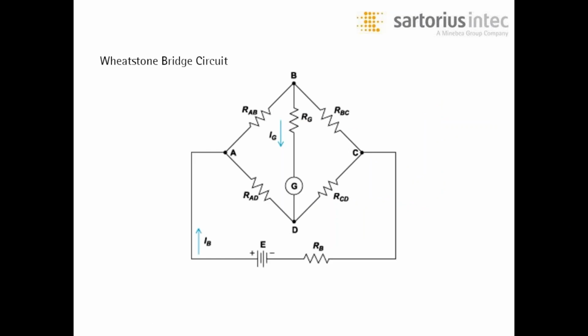As you can see, when they're configured in a Wheatstone bridge with 4 separate resistors connected as shown in a network, an excitation voltage, usually 10 to 12 volts, is applied to one set of corners, and the voltage difference is measured between the other 2 corners. At equilibrium with no applied load, the voltage output is 0 or very close to 0. When the 4 resistors are closely matched in value, that is why it's referred to as a balanced bridge circuit.